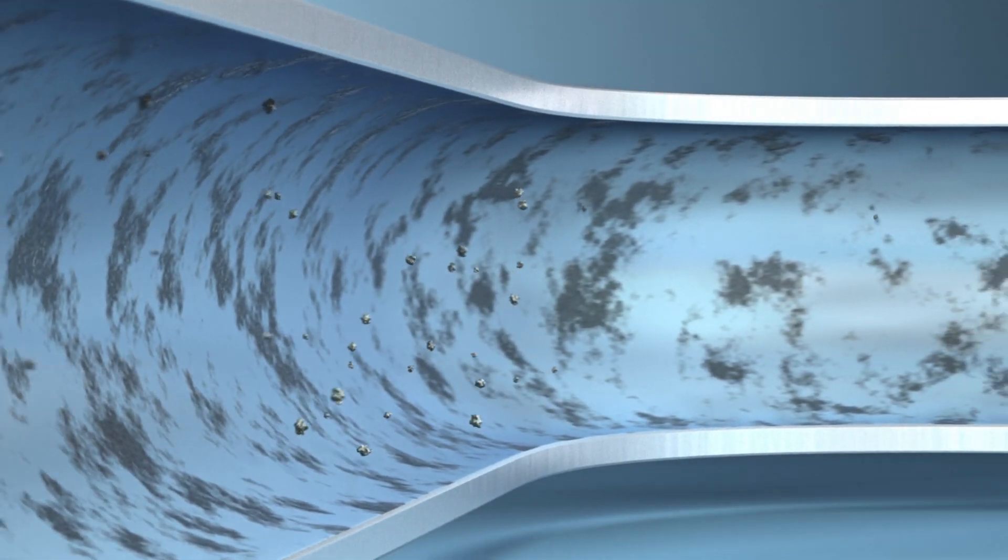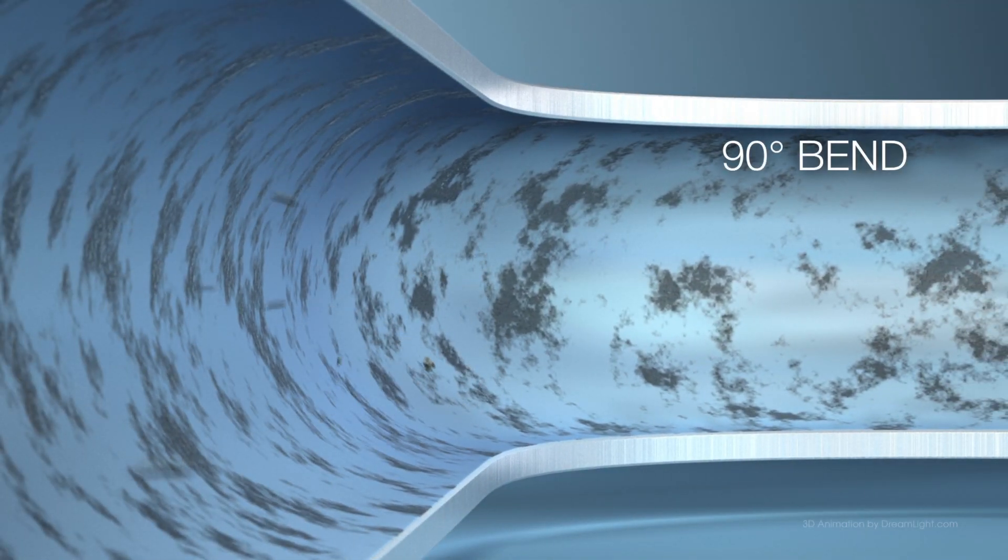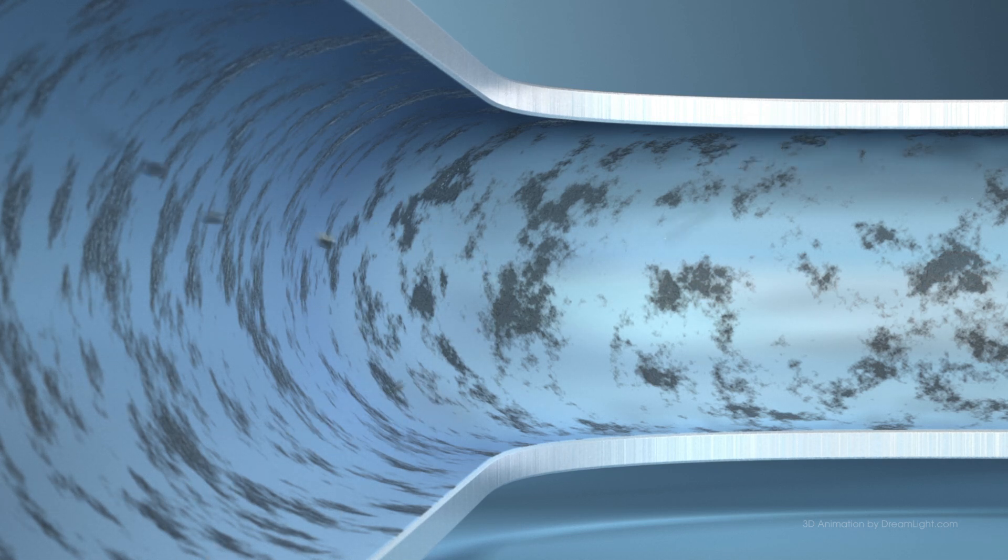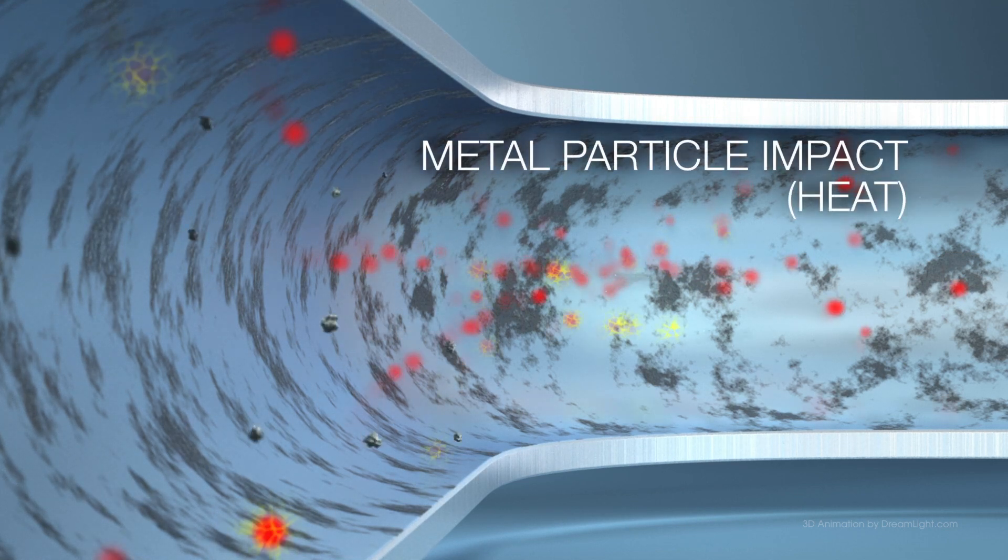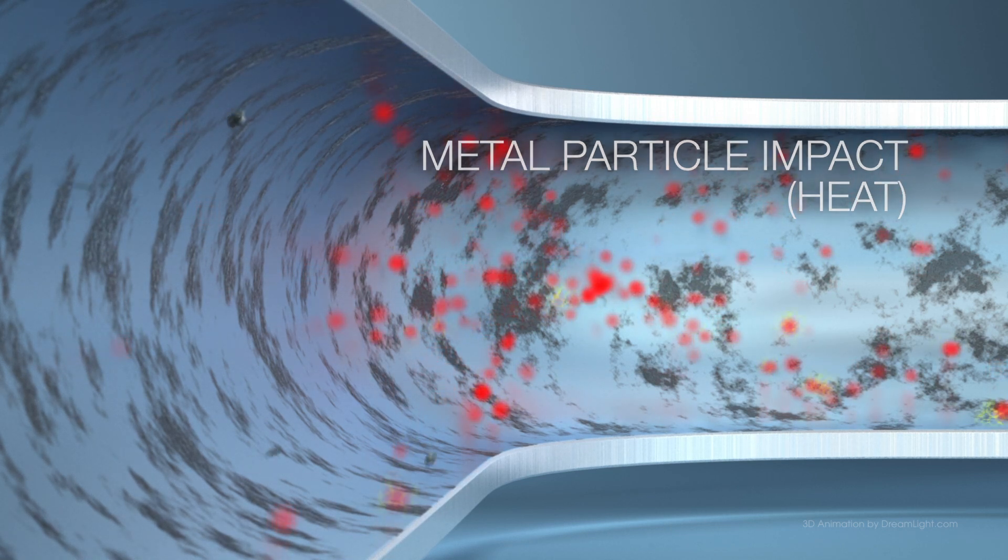Particles may travel at the same velocity as the service media. Bends in tubing or piping create a sudden change in direction where particles can impact the wall as they are being propelled by the service media. With sufficient kinetic energy, particle impacts may generate enough heat to create sparks.